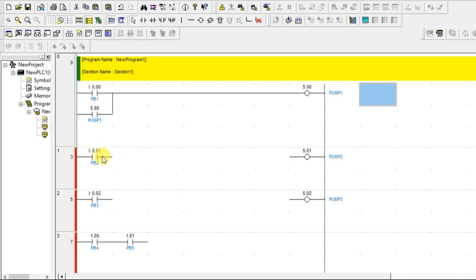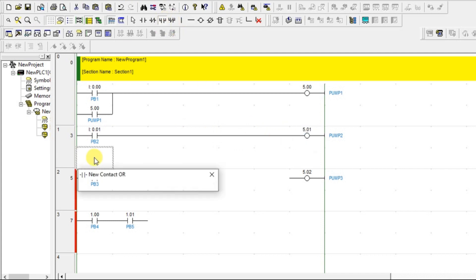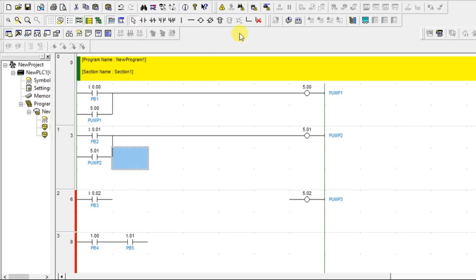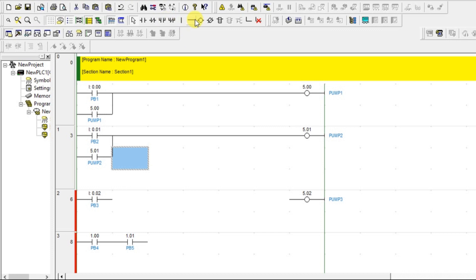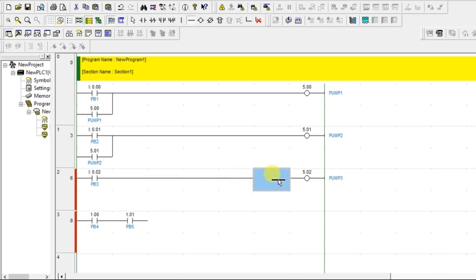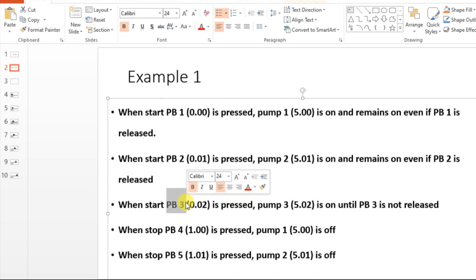Latching for pump 1 is done. Next, when PB2 is pressed, pump 2 should turn on and remain on even if released — same as the previous one. Add a horizontal line, add one parallel contact to PB2, and give the same address as pump 2. Done. The third statement: when PB3 is pressed, pump 3 is on until PB3 is not released — so if you release PB3, pump 3 should be off.